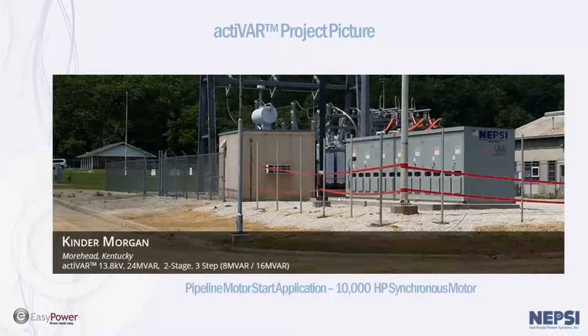Here is another project we did with the system to assist with a 10,000 horsepower synchronous motor start. This is a 13.8 kV application, and it's 24 megavars again, but it's in 2 stages, 3 steps. In other words, there's an 8 megavar step and a 16 megavar step, and the actiVAR control will turn on both the 8 and 16, or just the 8 or just the 16, to meet the requirements for the substation.